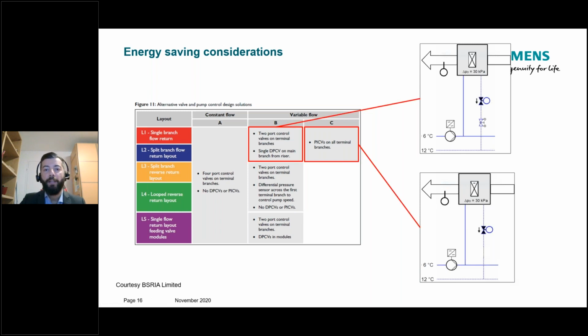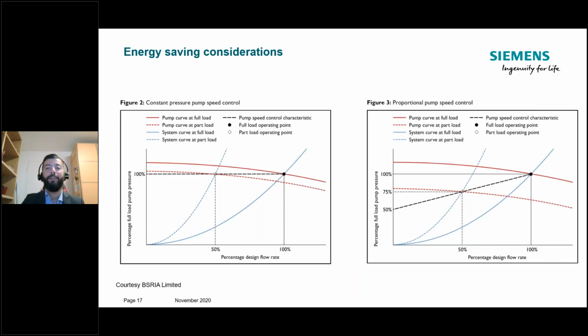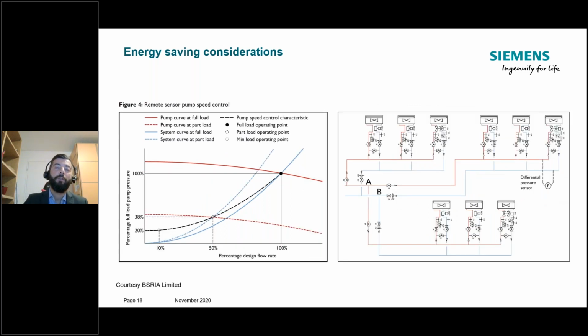And very interesting is that you can check to what extent the energy saving can go if you mix the right combination of valves with the correct pump control strategy. What is the pump control strategy? Well, as you probably know, variable speed pumps can be controlled in at least 3 of the main or most known ways. There is constant pressure control, you see here, and proportional variable pressure, you see the black dotted curve, which is basically the characteristic of the pump along the flow and the head of the pump itself, the pressure. And also interesting is that you can control the pump by means of a remote sensor.